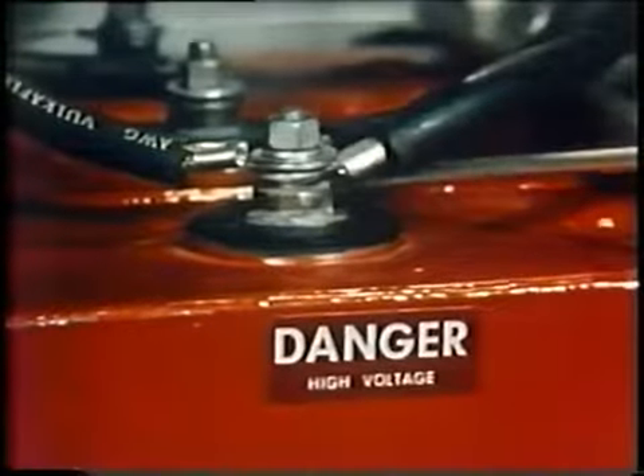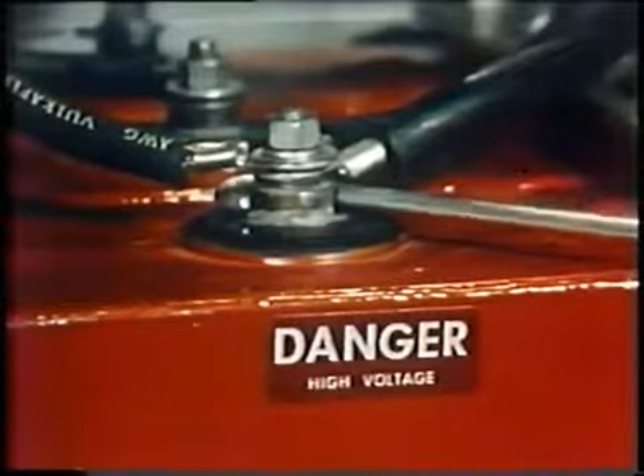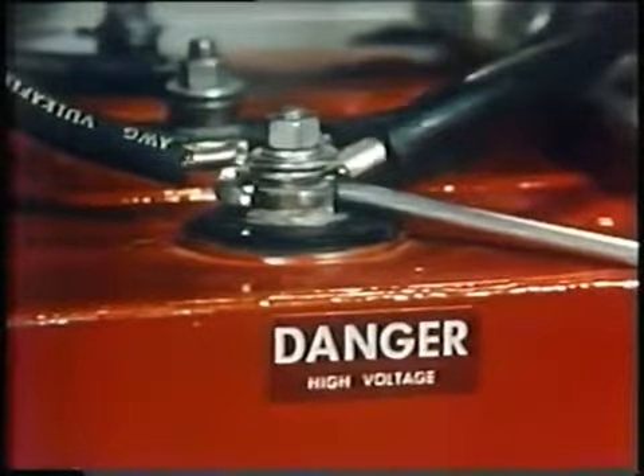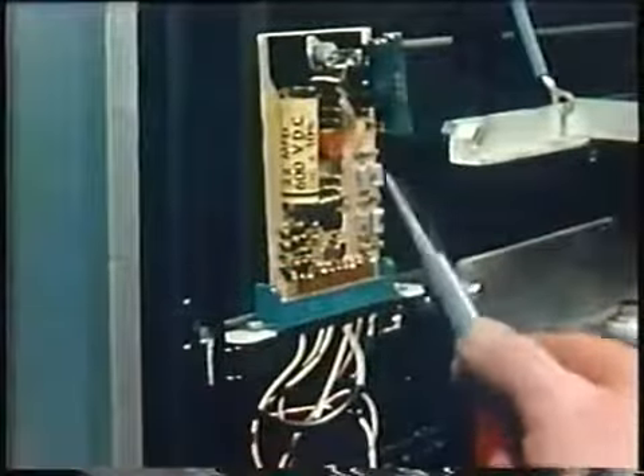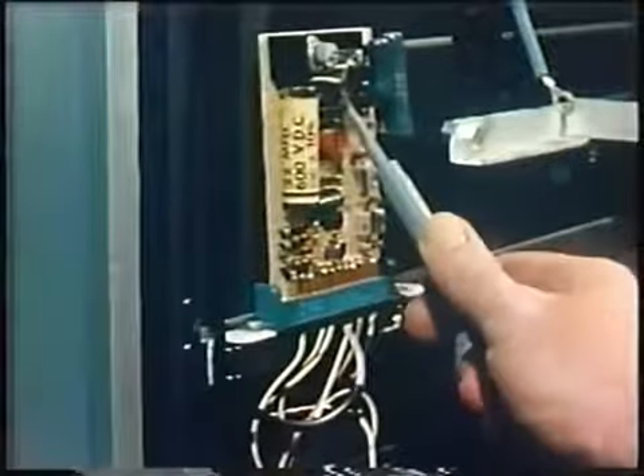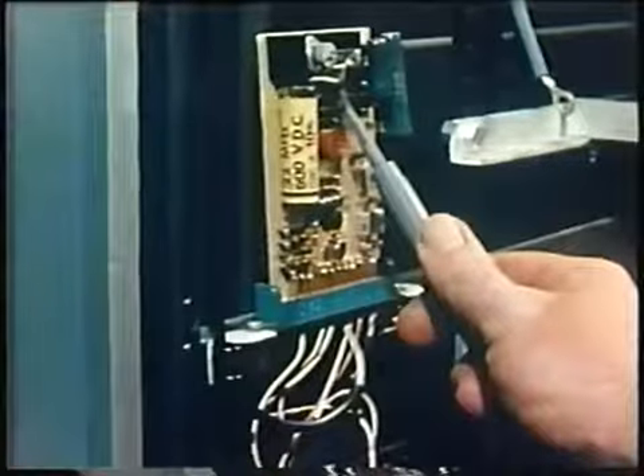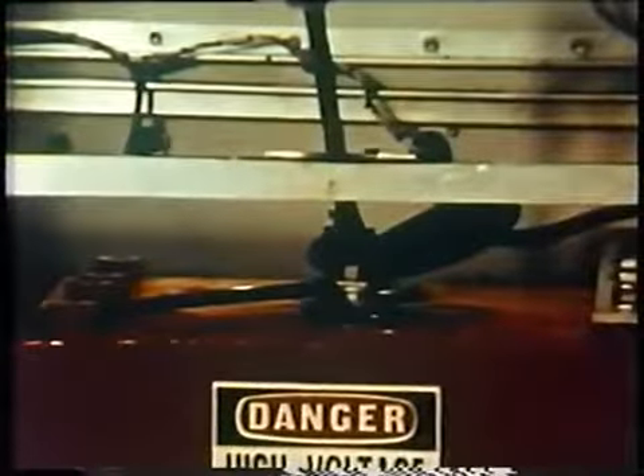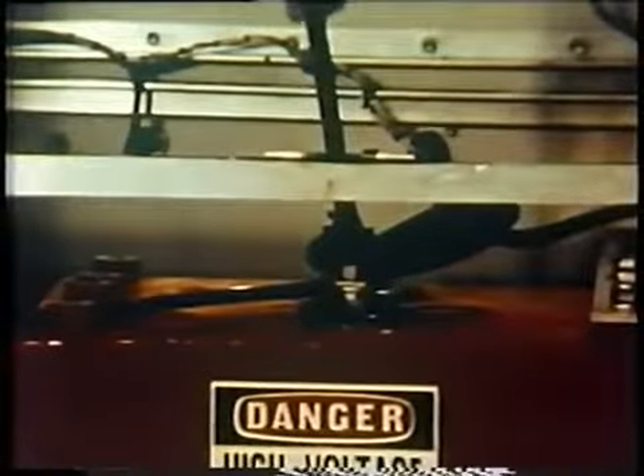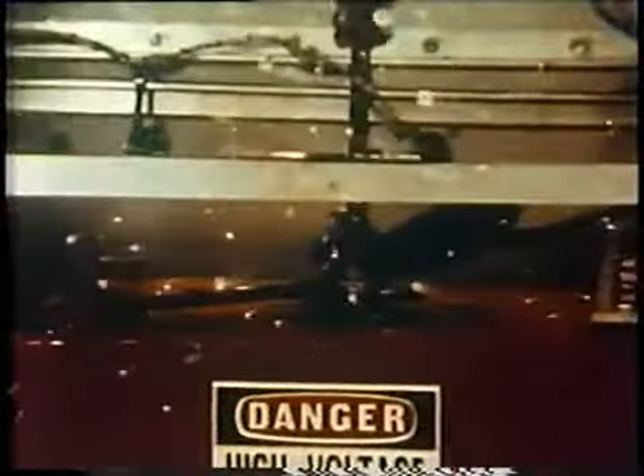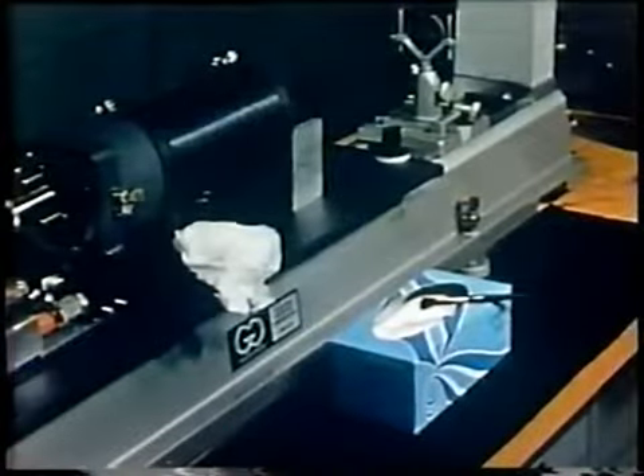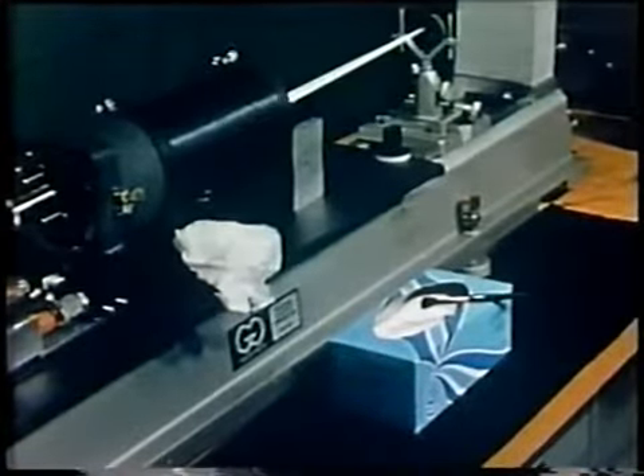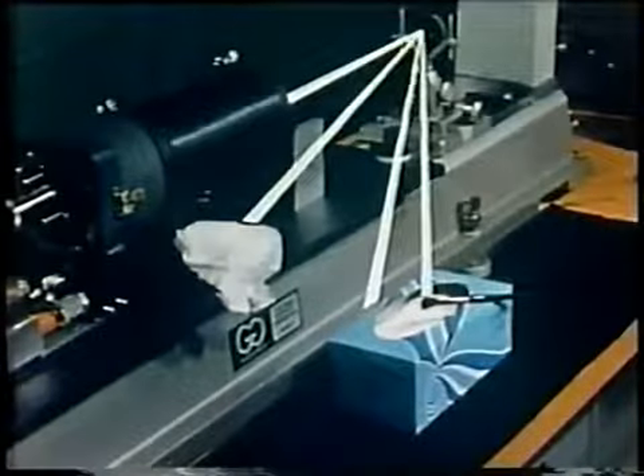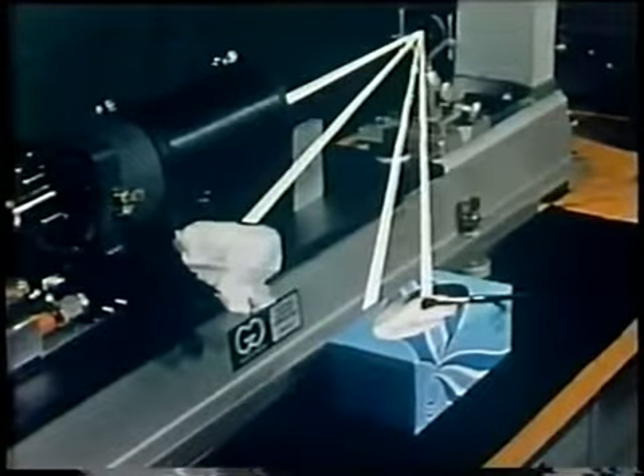To make certain it is safe to work inside, all high voltage points must be grounded and remain grounded. This will dissipate any stored charge remaining in the capacitor. This demonstration shows what may happen if it remains charged. Many of the materials normally used around laser operations are flammable, and specular reflections could set them afire.